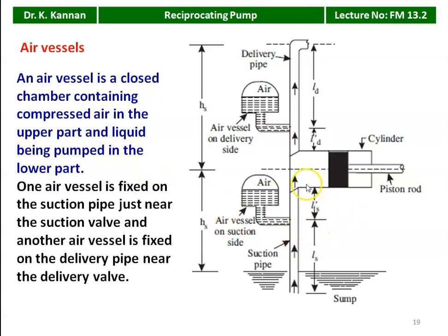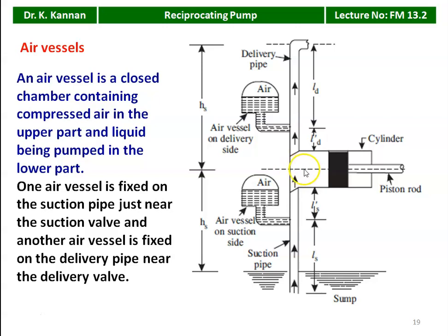The purpose of the air vessel: when the piston is reciprocating backward, the suction valve opens and liquid is drawn into the cylinder due to pressure difference. During this suction stroke, water in the air vessel is also drawn in. During the delivery stroke, when the piston moves from right to left, the water is compressed, the delivery valve opens, water is delivered, and excess water is stored in the air vessel on the delivery side. During the next suction stroke, the liquid in the delivery-side air vessel is discharged to the delivery tank, ensuring continuous supply of liquid in the delivery pipeline.